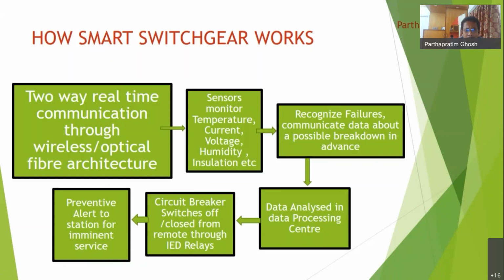A very important part, which is singularly an attribute of the smart grid, is the preventive alert to the station for immediate service, because there are sensors which can preemptively sense that, although today there is no failure, maybe in the coming weeks, months, or years a certain part of the substation may fail, because there are signals for these future failures. This data, through sensors and wireless communication, is collected, analyzed, and fed back to the substation for taking advance action before the ultimate failure. So that is one of the very important aspects of smart switchgear and the smart grid as a whole.